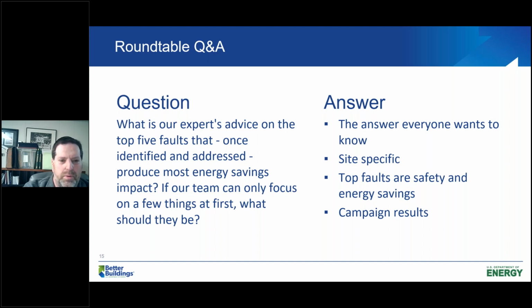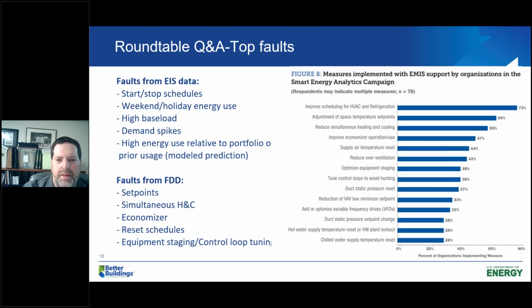I'll go a bit quicker here — this is a list of the top ones found from the campaign, the top 5 in terms of EIS and FDD. From the EIS side, a lot of it's scheduling, things left on, high base load or demand spikes. From an FDD point of view, simultaneous heating and cooling shows up, but that can be caused by a lot of things — leaking valves, programming issues — though it's generally the biggest energy one. That and economizers are the two big ones in terms of energy savings, but from the campaign we have a good list of what they are.